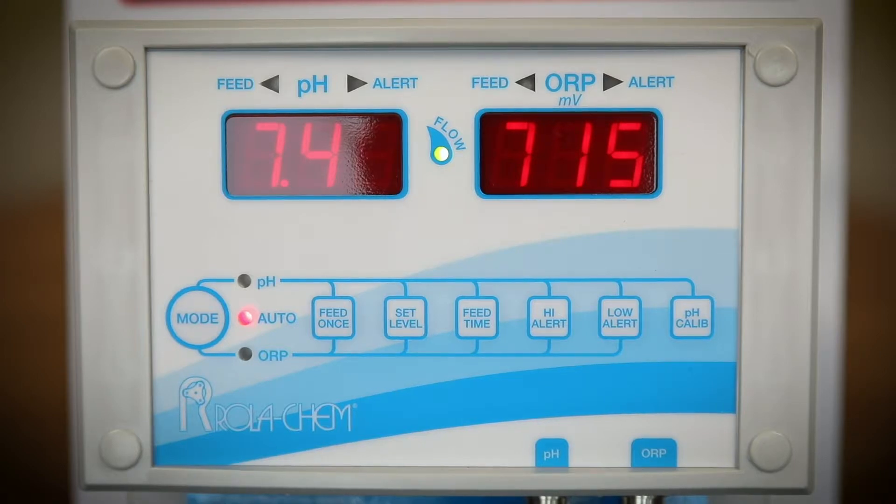Should the flow cell read differently, remedy the flow restrictions to the flow cell. Rola-Chem recommends that the probes be cleaned every 30 days, as probes that are calcified or dirty will not read the chemistry correctly.